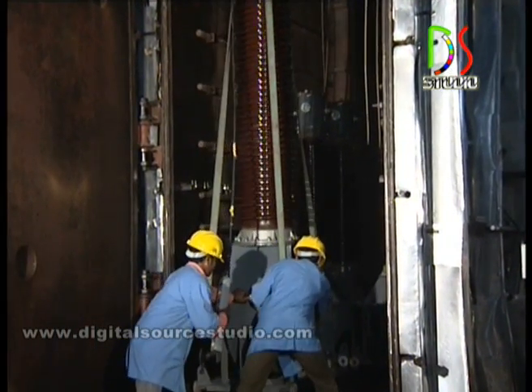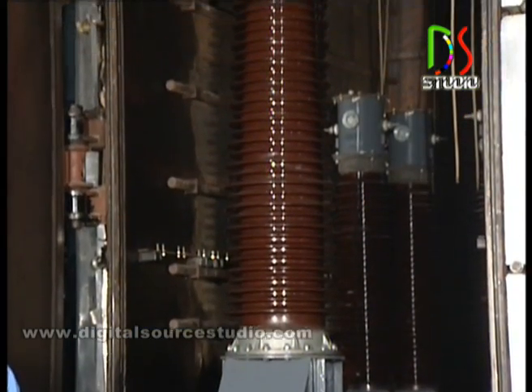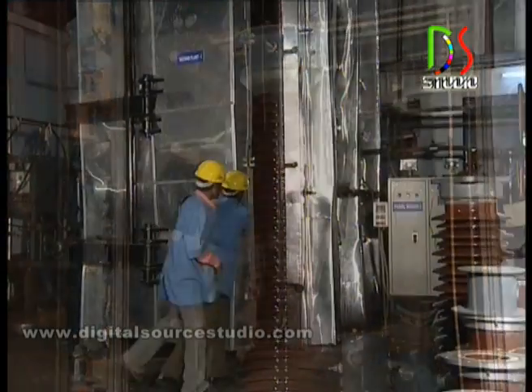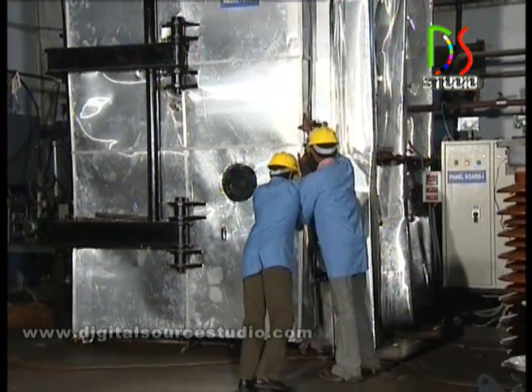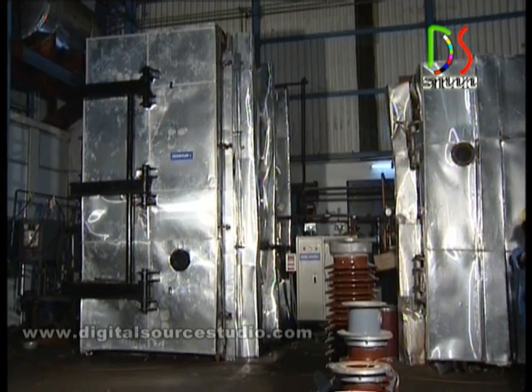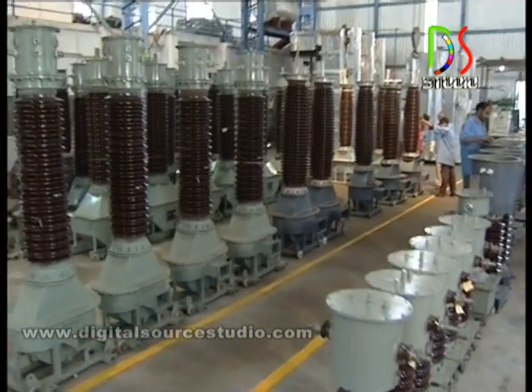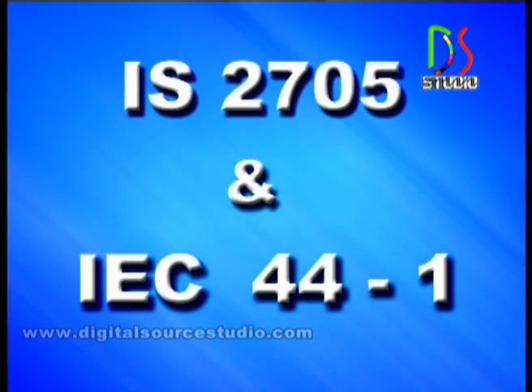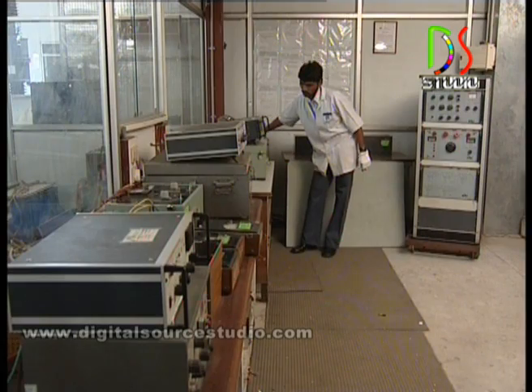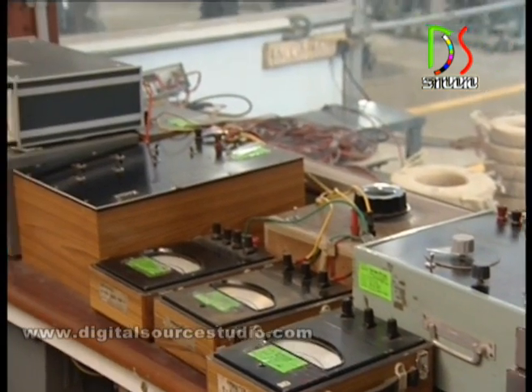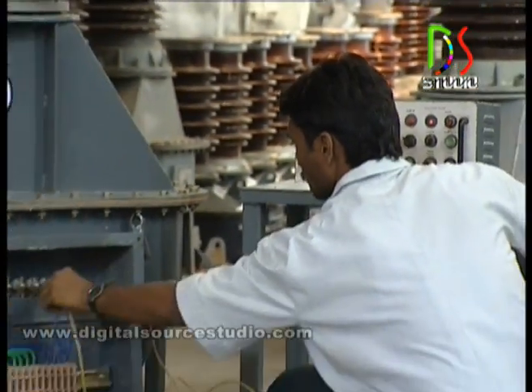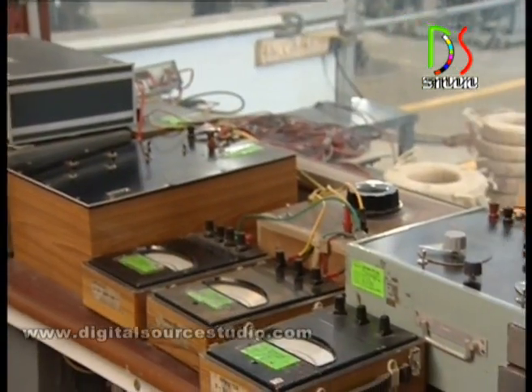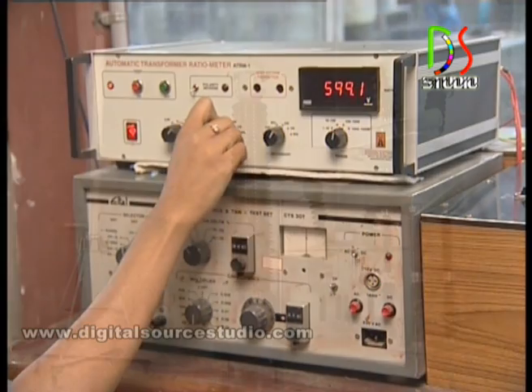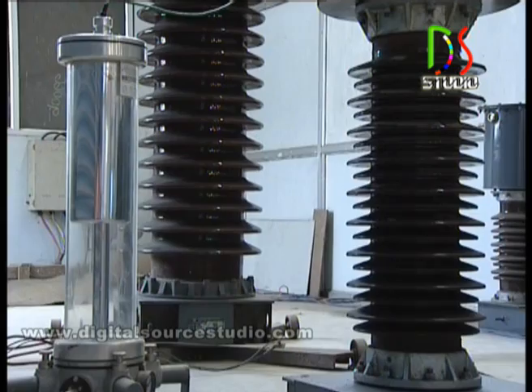The assembled unit is loaded into a vacuum and heating chamber and subjected to a special vacuum impregnation process. The unit is then filled with transformer oil after the specified time, temperature, and vacuum are attained. The current transformers are completed and subjected to tests as per IEC standards: accuracy test, overvoltage interturn test, high voltage test on primary and secondary, knee point voltage test for special purpose core, composite error test for protection core, partial discharge test, tan delta test.